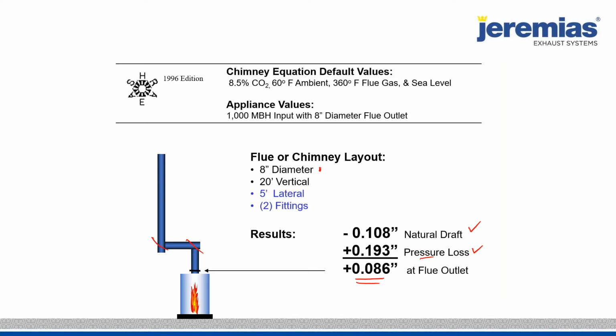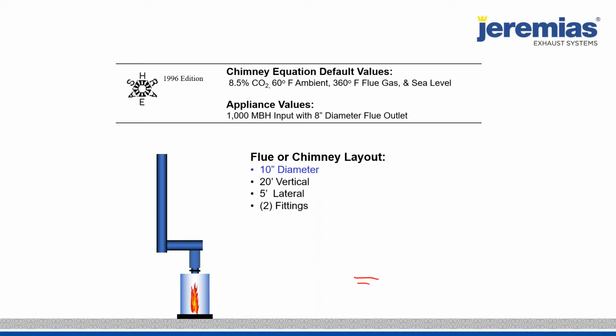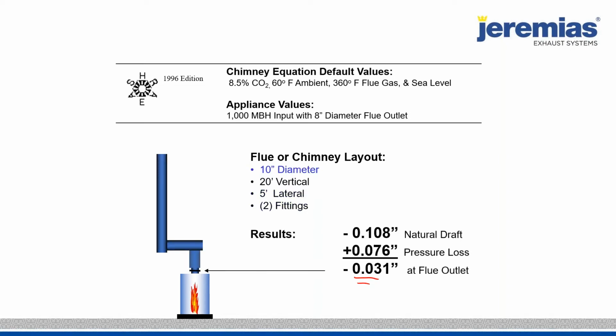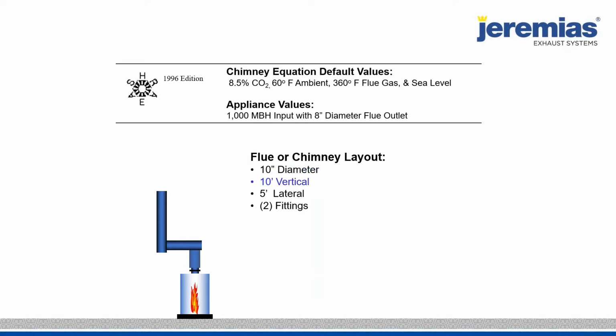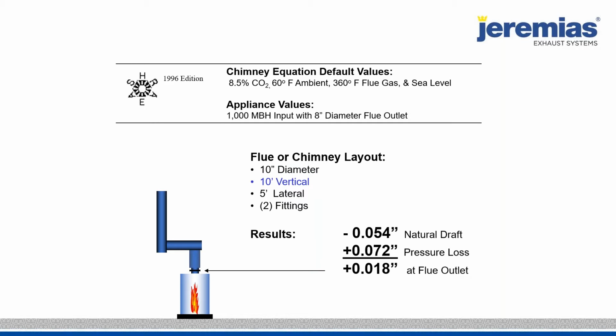So on the next slide, we're going to change the diameter to 10, redo the calculation, and now we're back to a slight negative pressure. So you see we went from a 0.19 pressure loss to a 0.07. So again, we're back to safe venting. Let's say you only had 10 feet of stack. Now the draft is half as much. Now you're back to a positive vent pressure. What do we do? We use a 12-inch diameter.